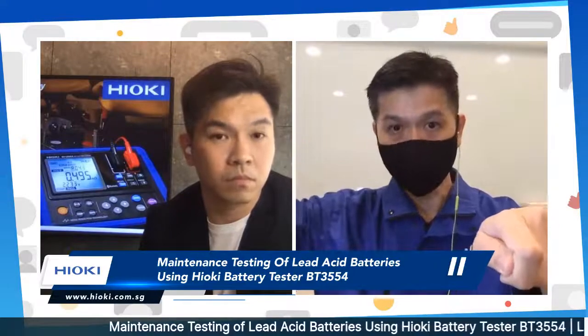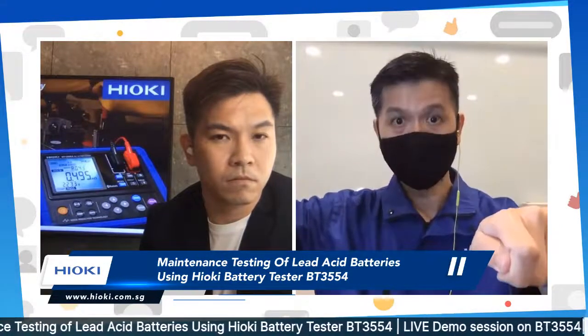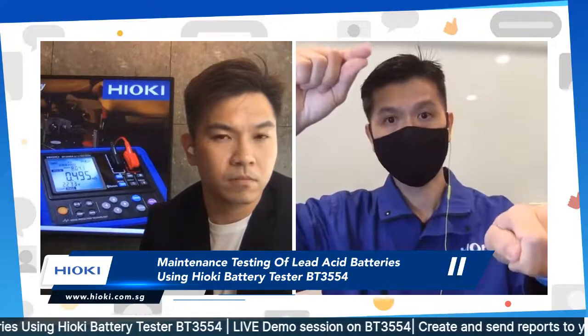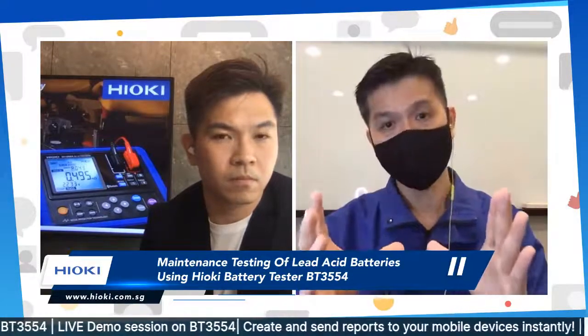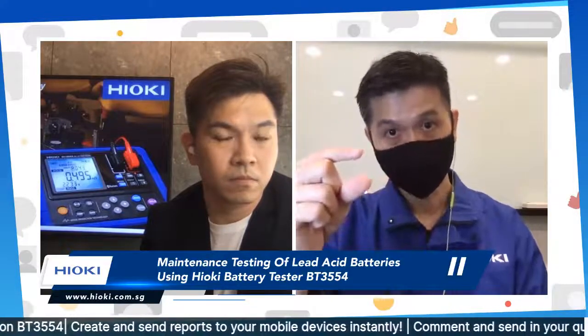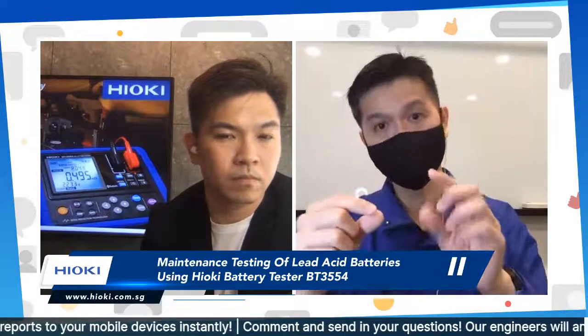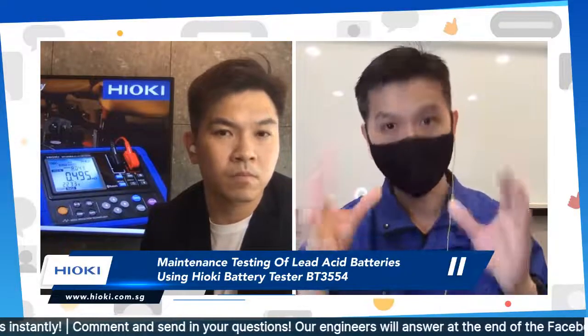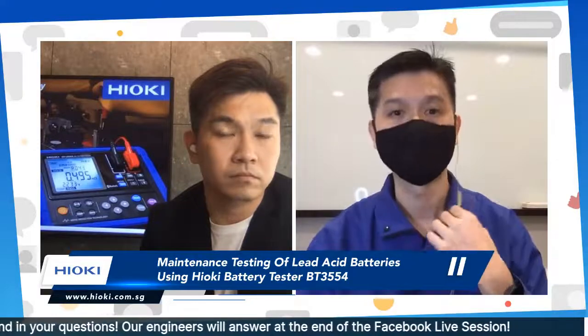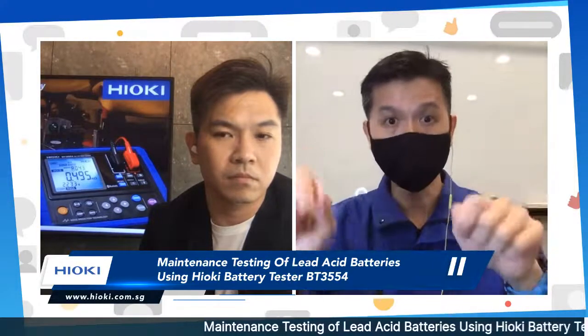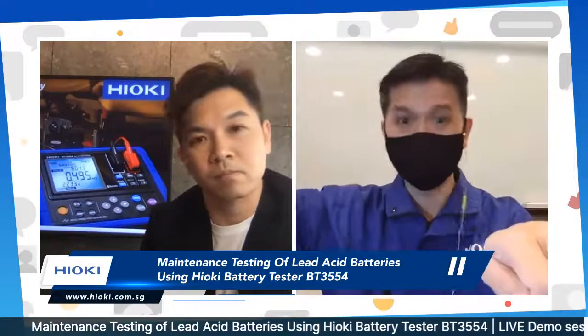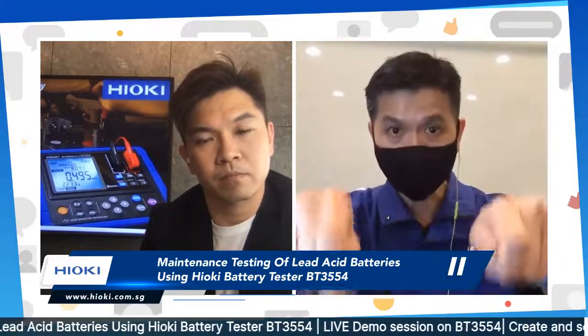When that happens, when the metal enclosure is touched on, the voltage will suddenly spike up. So the only way to save the battery tester is the fuse. When the fuse detects a very high voltage, it will trip to save the BT3554 circuit. That's the reason why that happens. So the only way to avoid blowing the fuse is to always measure by touching the positive and negative terminals only, and never suddenly touch the metal enclosure.